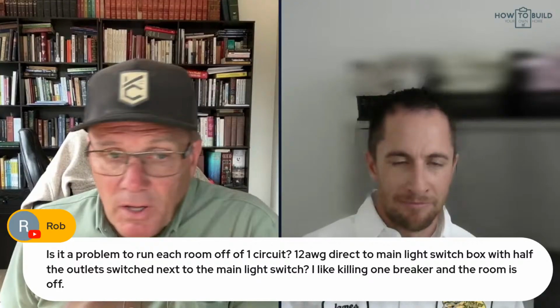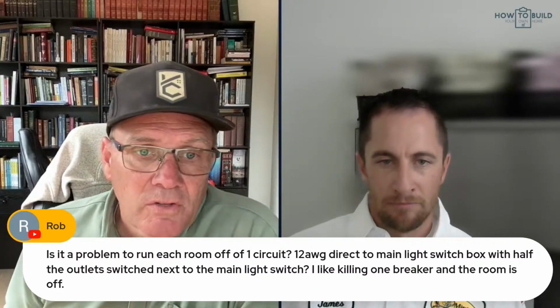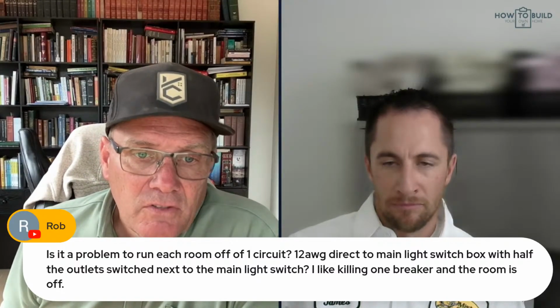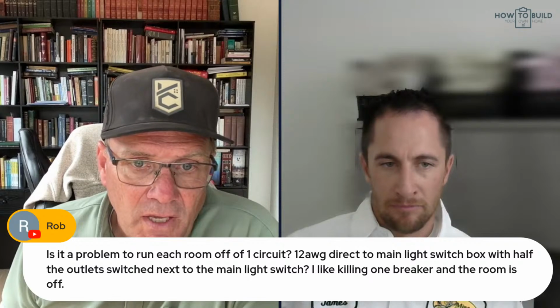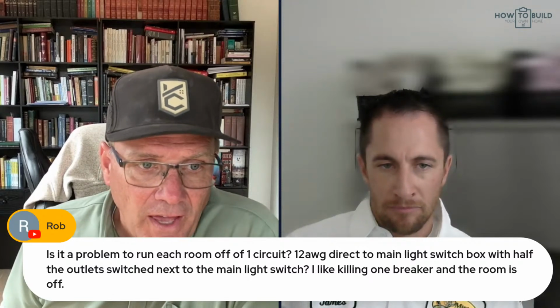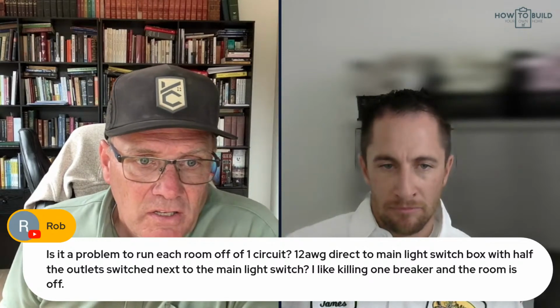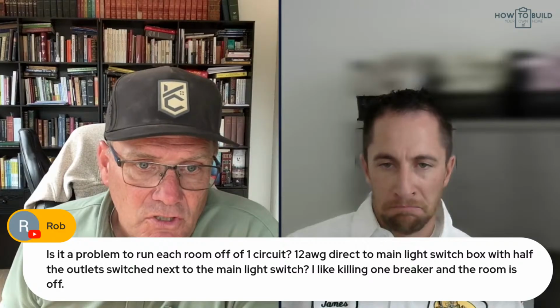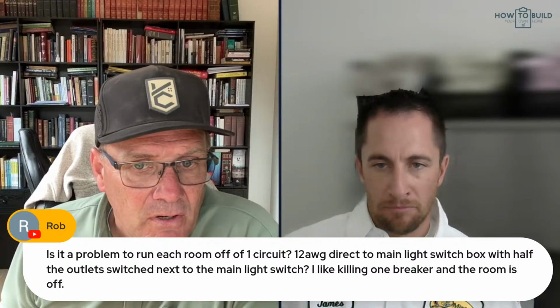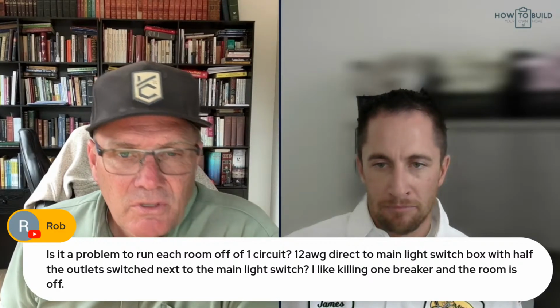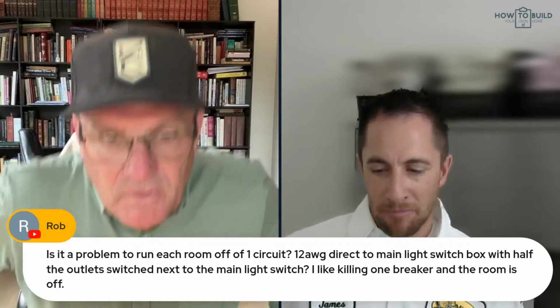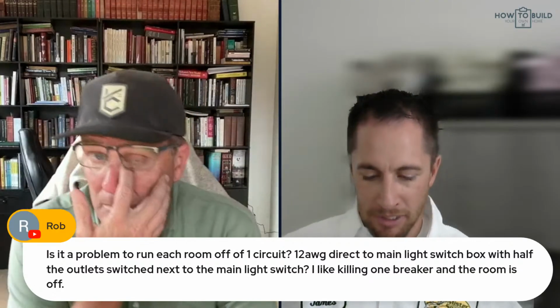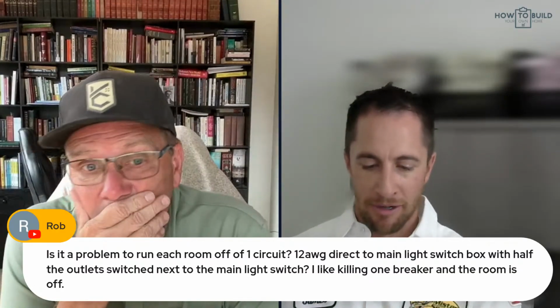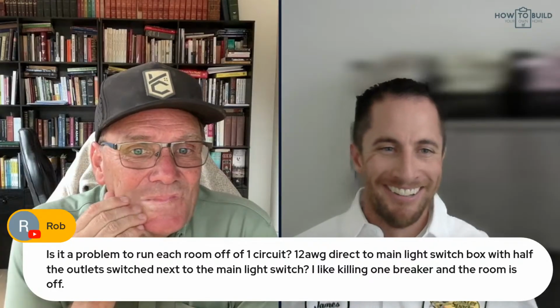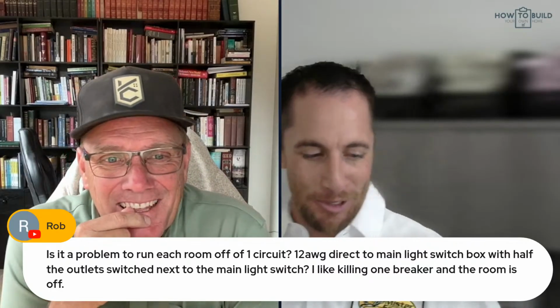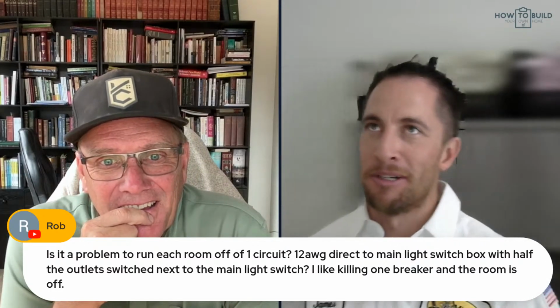Is it a problem to run each room off of one circuit, 12 AWG direct to the main light switch box, with half the outlet switched next to the main light switch? I like killing one breaker and the room is off. What do you think about that, James? Well, that puts you in a position where you have more power in your room than most people do. Usually it's 2 or 3 rooms. They're trying to meet code but do it as cheaply as possible.